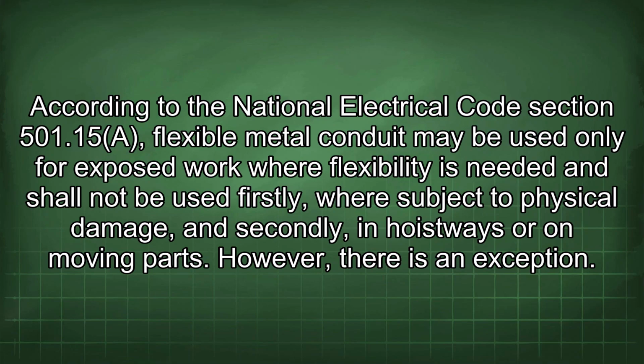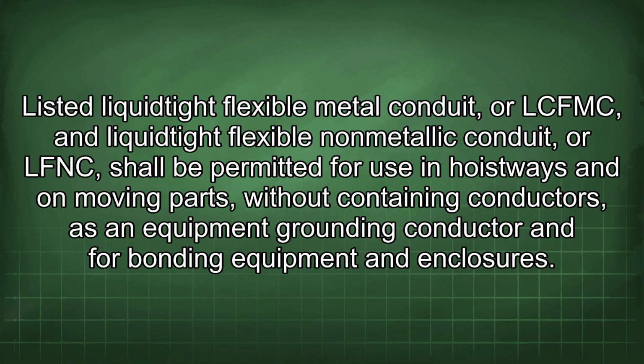According to the National Electrical Code Section 501.15(A), flexible metal conduit may be used only for exposed work where flexibility is needed and shall not be used, firstly, where subject to physical damage, and secondly, in hoistways or on moving parts. However, there is an exception. Listed liquid-tight flexible metal conduit, or LFMC, and liquid-tight flexible nonmetallic conduit, or LFNC, shall be permitted for use in hoistways and on moving parts, without containing conductors, as an equipment grounding conductor and for bonding equipment and enclosures.